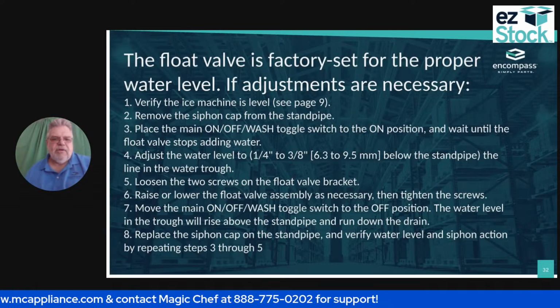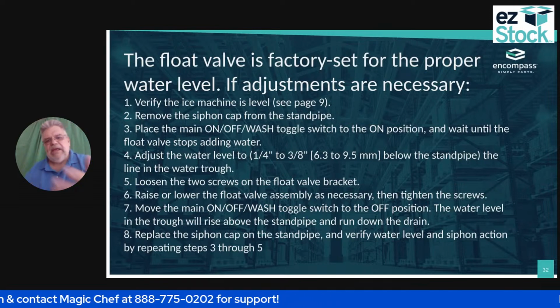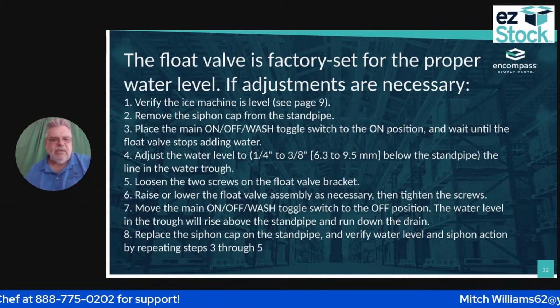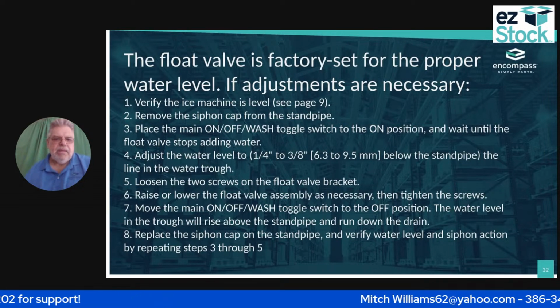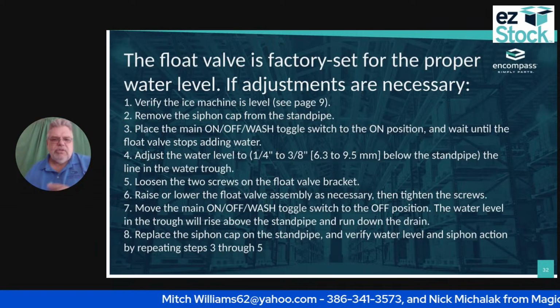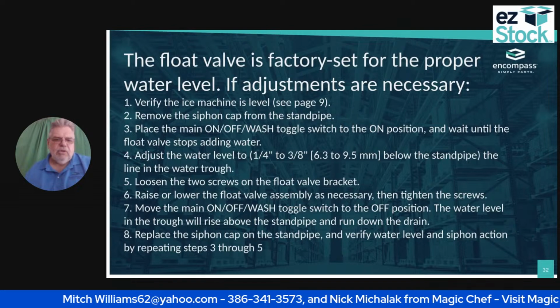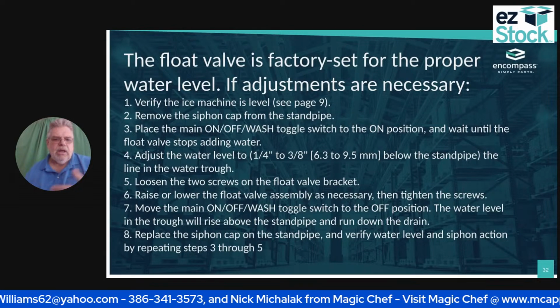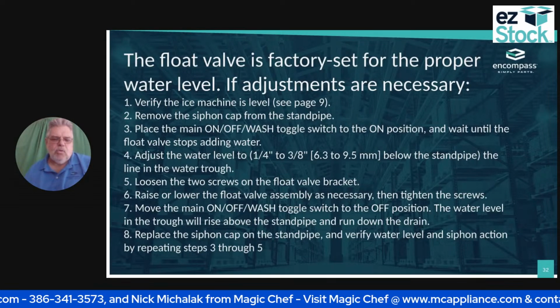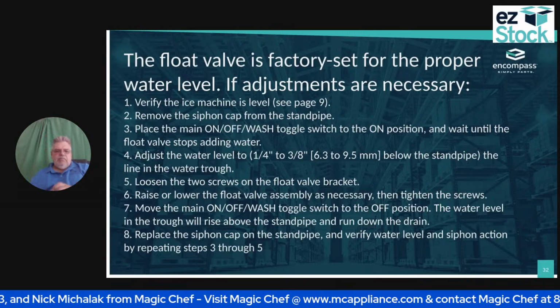Okay, so I'm going to verify the ice machine is level. That also affects my float valve. I'm going to remove the siphon cap. I'm going to place the main on-off wash switch to the on position. Wait for the float valve to stop filling with water. I'm going to adjust the float valve to 1/4 to 3/8 below the standpipe.